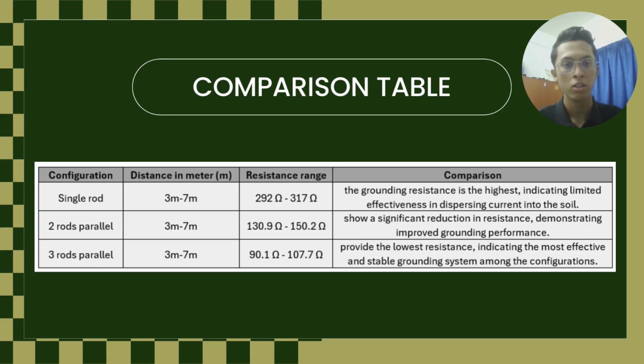To make these findings more actionable, we have summarized the data in this comparison table. First, we have the single rod. The single rod configuration represents our baseline, with a resistance range of 292 ohm to 317 ohm. It shows the highest resistance. This indicates a limited ability to disperse current into the soil effectively, which could pose a risk in high load scenarios. And the second one is the two rod parallel setup.